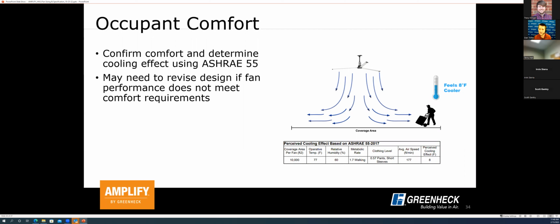This can also be used to define the cooling effect someone would experience based on those variables we talked about earlier, and can help you determine how much to offset your cooling set point when applying an HVLS fan. Here's a screenshot of the output from that cooling effect calculation from our CAPS and eCAPS program. At this point in the design process, we start to get into a bit of iterative design—we've identified building type, application, and performance requirements, checked occupant comfort, and determined whether we're in a thermally cold or thermally warm environment. We might have to go back and relook at our layout or fan selection to get back to a more thermally neutral environment.